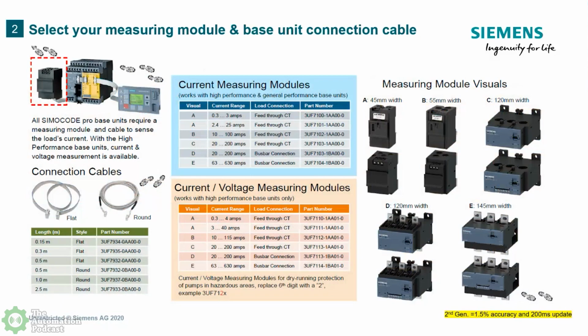To talk to the basic unit, I can go up to 2.5 meters away to where you can put your 480 volt on one side of the cabinet, and then your 110 to 24 volt on the other. And then you can look at your arc flash and your PPE for that, opening which side of the cabinet, and be able to stay on the lower cal PPE that you need because you're only opening up to 24 volts or 110.